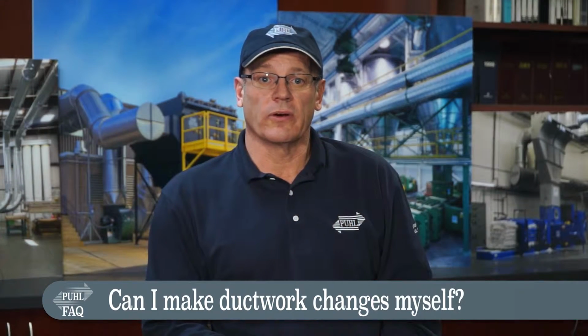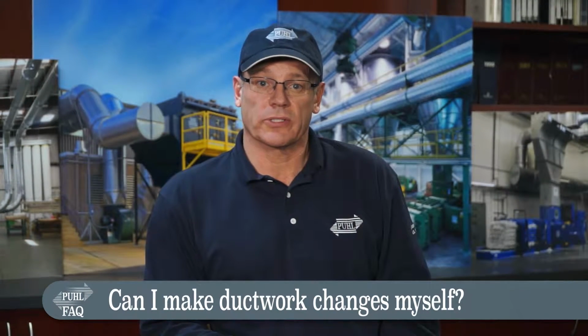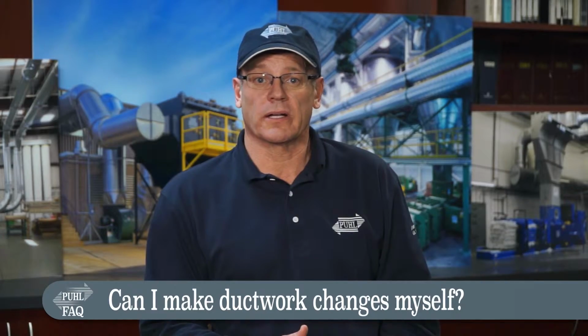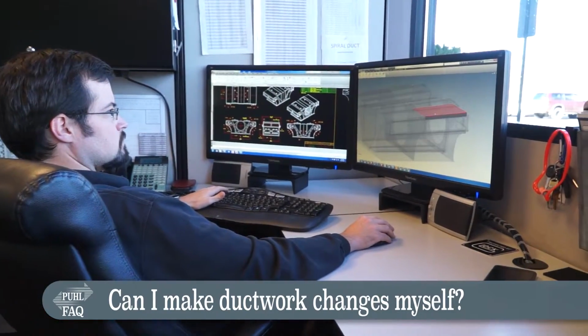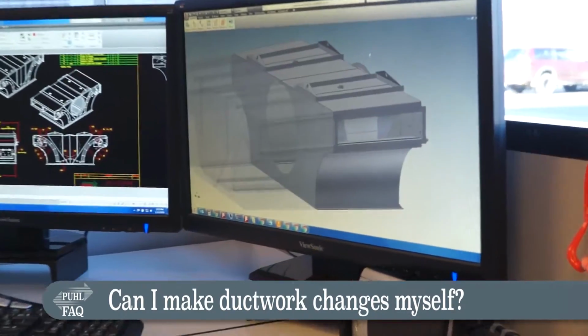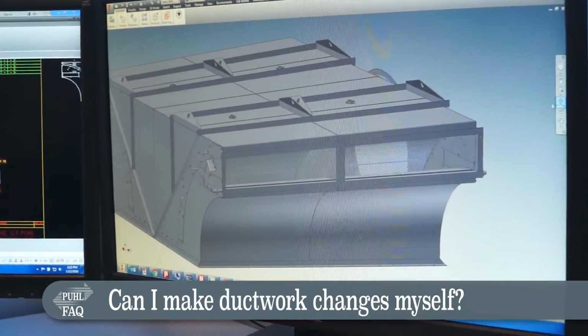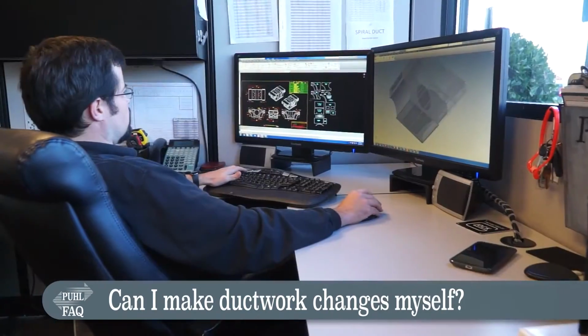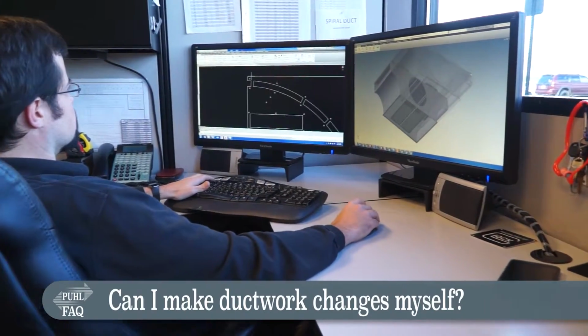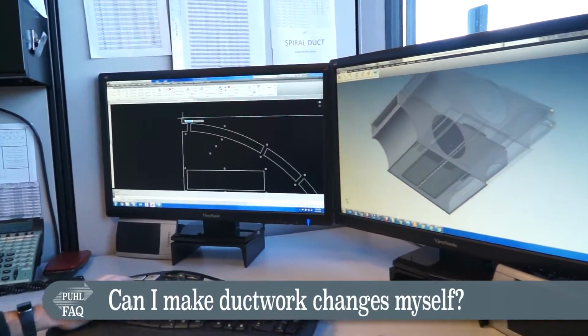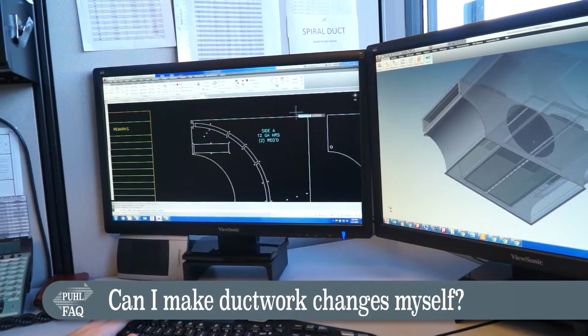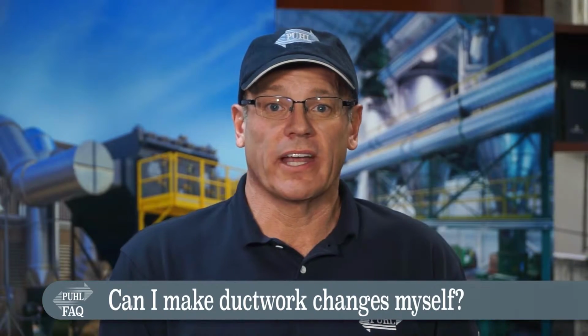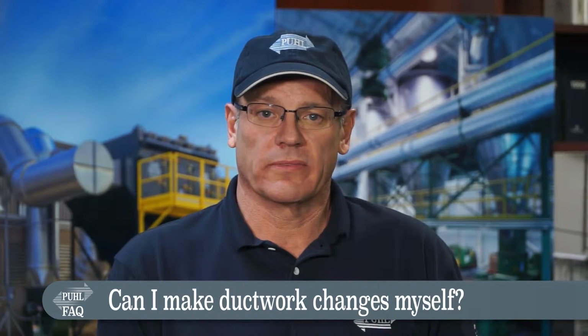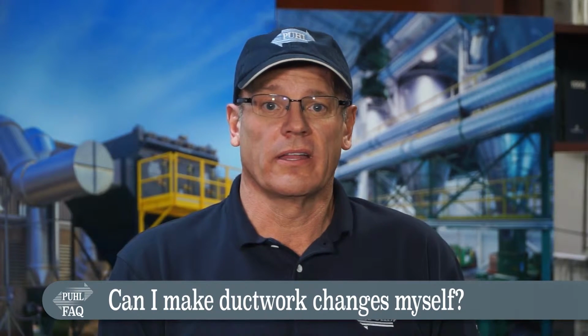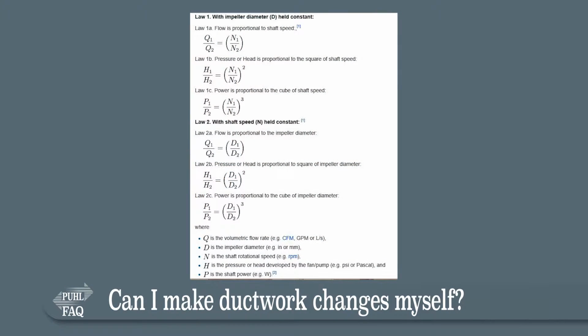Fire hazards aren't the only reason to steer clear of do-it-yourself ductwork changes. Another reason has to do with your bottom line. The issue is performance of the duct system. By not optimizing the distribution of the suction and matching the blower to what is needed, you can be wasting more money in electric power usage in just a couple of months versus what you save by designing and installing the ductwork yourself. Radial blade blowers convey air and material based on the laws of physics. Of particular interest is the fan law that states for a given blower, the power required is proportional to the cube of the shaft speed.